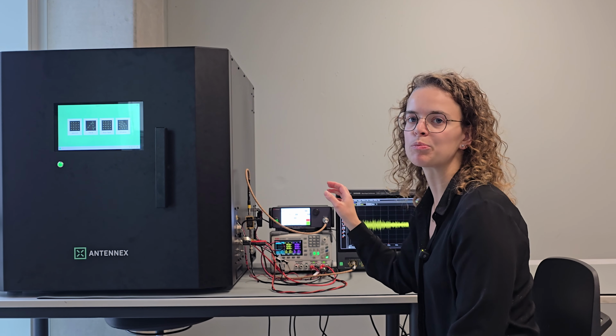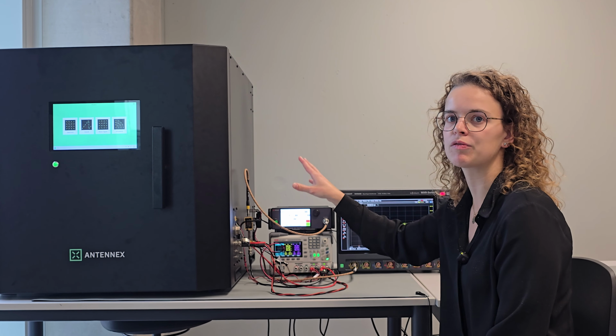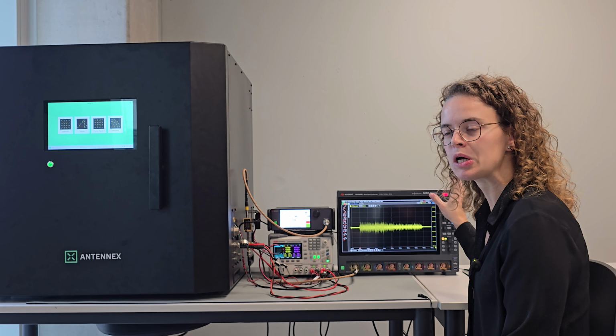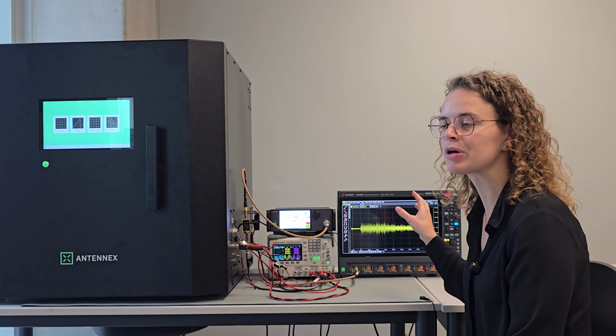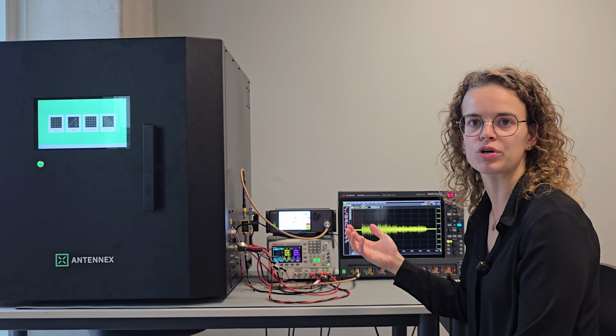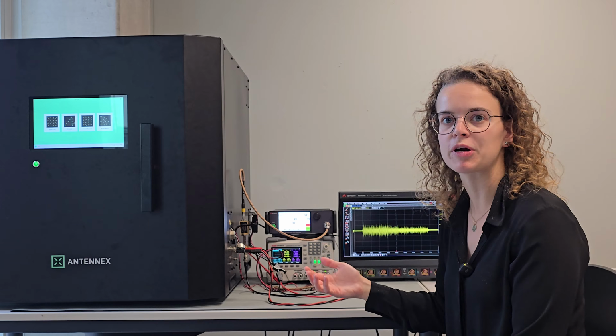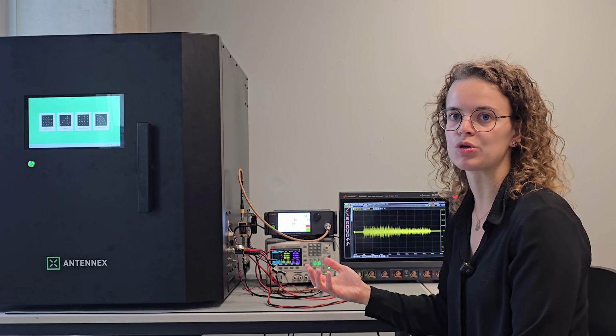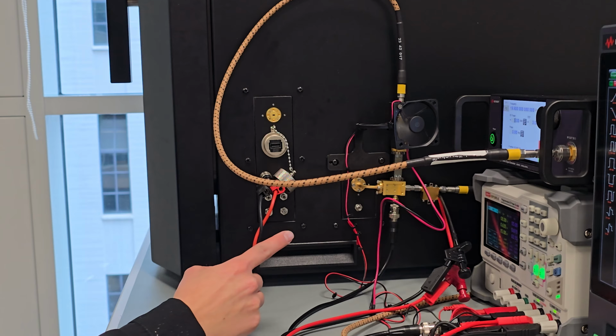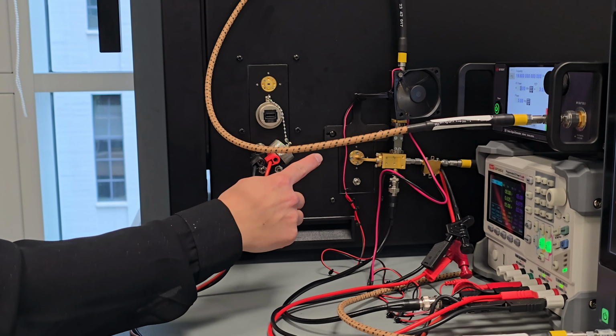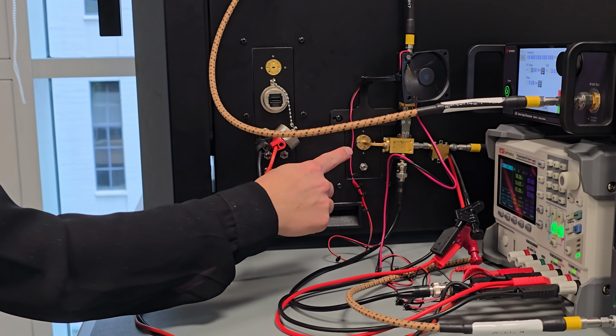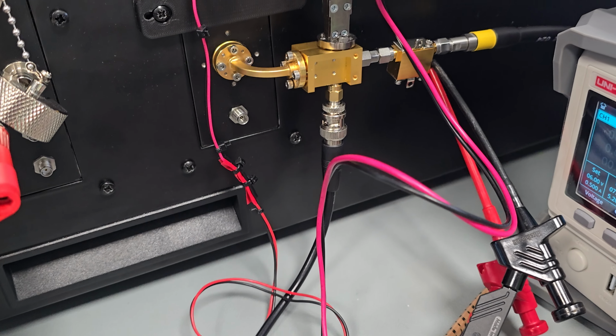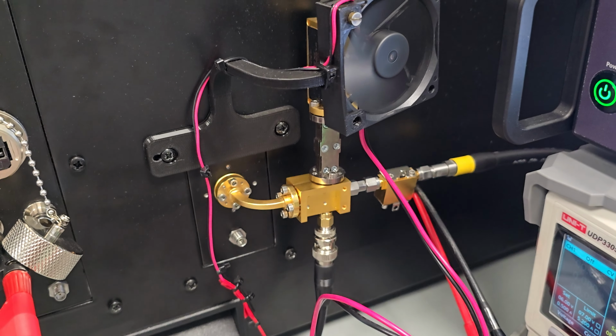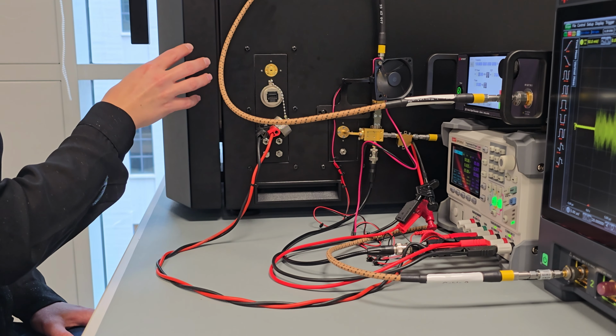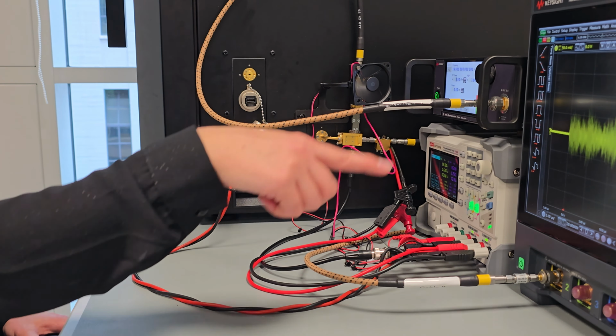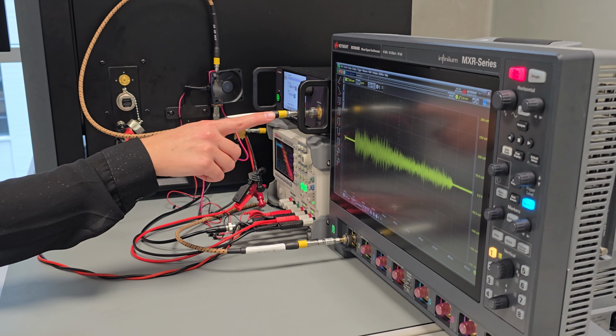So just with a simple Ethernet connection between the reverberation chamber and the oscilloscope, we will capture the data of the chirp and we will post-process that to get, for example, the chirp linearity, the power spectral density, but also chirp rate and those kind of metrics. So at the side of the chamber, we have the external path which we will calibrate with the external calibration, which consists of a mixer to downmix the signal from the FMCW radar, which is operating at 60 gigahertz, to a maximum of 6 gigahertz, which the oscilloscope can capture.